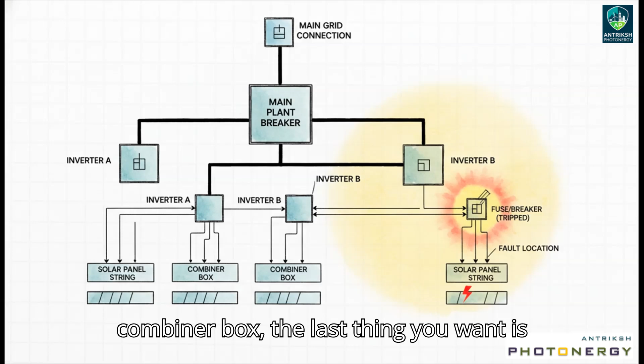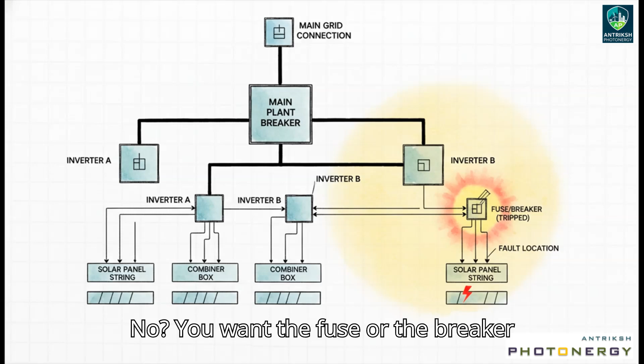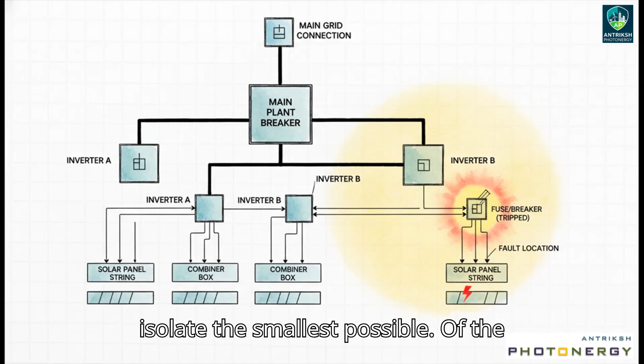Think about it. If you get a small fault in one single combiner box, the last thing you want is for the main breaker for the entire plant to trip, right? That would be a disaster. No, you want the fuse or the breaker that's closest to the problem to open first. Good coordination means you isolate the smallest possible part of the system, and that does two things. It keeps the rest of the plant making money, and it makes finding the fault way, way easier for you.